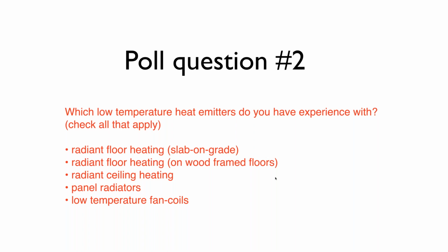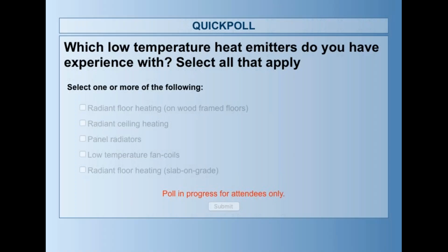Again, you have a lot of options, and I should mention this, you don't have to necessarily pick one of these options and just use it throughout the entire house. You might choose to run floor heating in some areas, like in a basement, and maybe panel radiators or fan coils on the second floor. So you can mix a lot of these together. Just keep in mind that we don't want that water temperature under design load to go above 120 degrees.